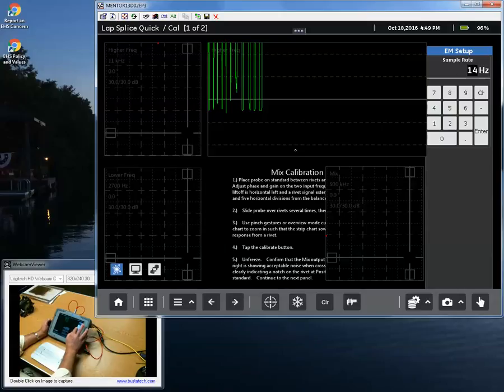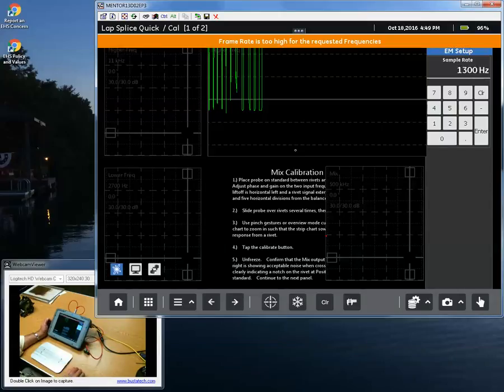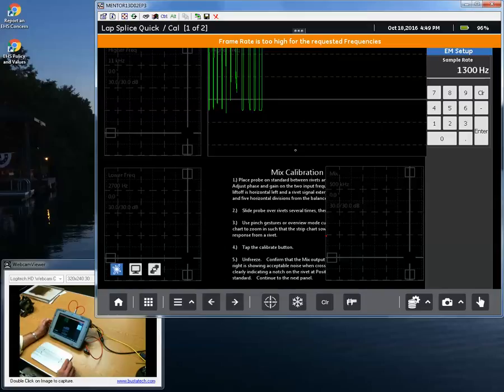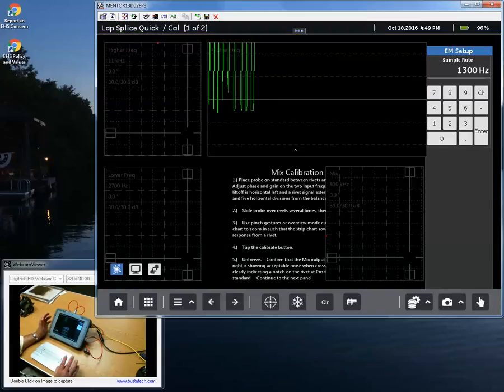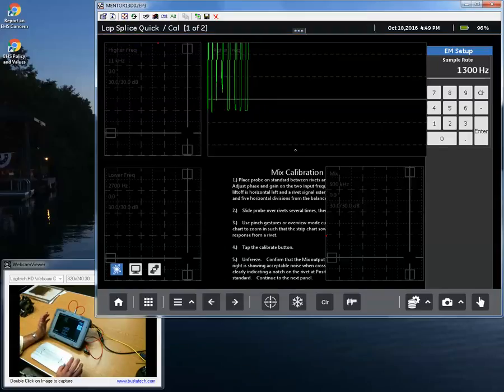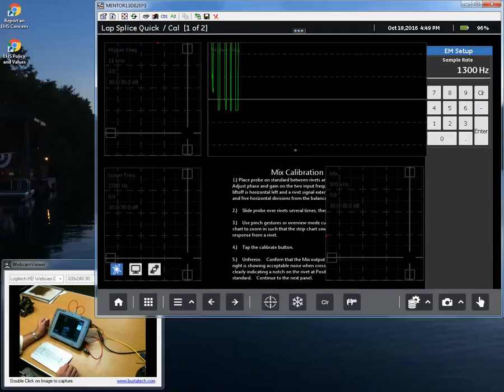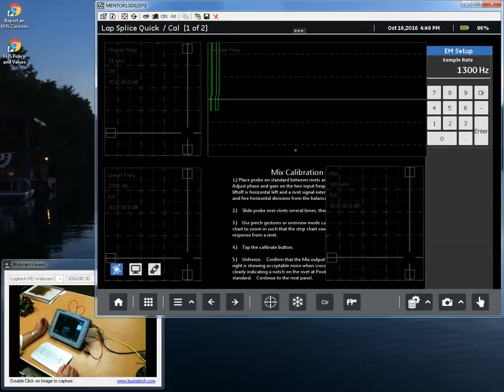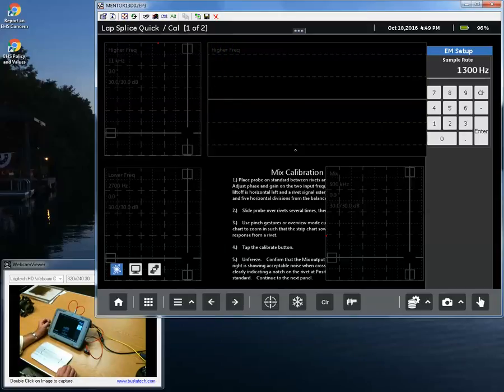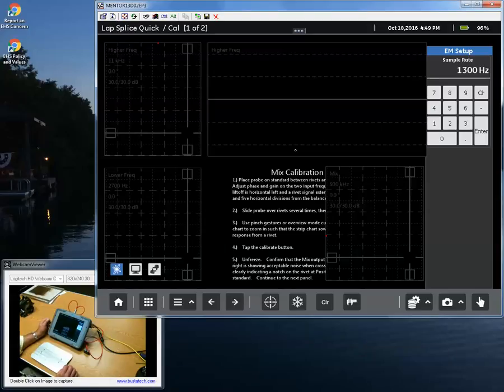If our sine wave is 2.7 kilohertz, we can't really run our sample rate at more than half of that. So 1,300 hertz works. If I try to go to 1,400 hertz, the instrument says the frame rate is too high for the requested frequencies. Frame rate and sample rate are interchangeable terms. Like many other things in Eddy Current, there are multiple names for pretty much the same thing.